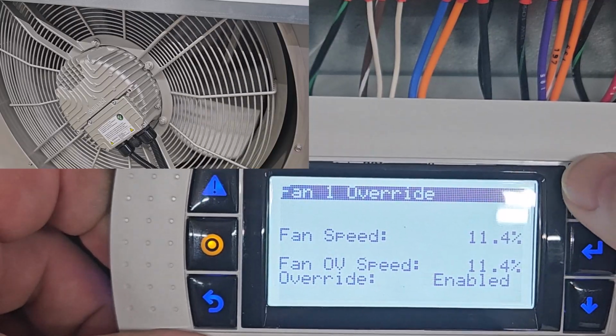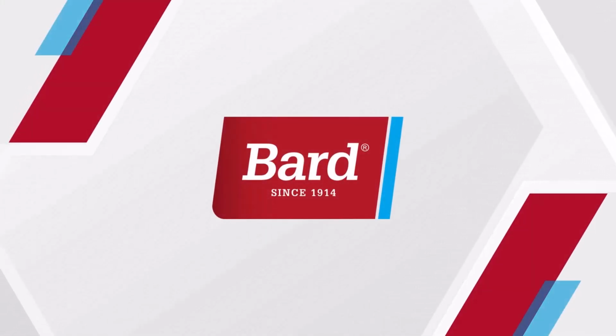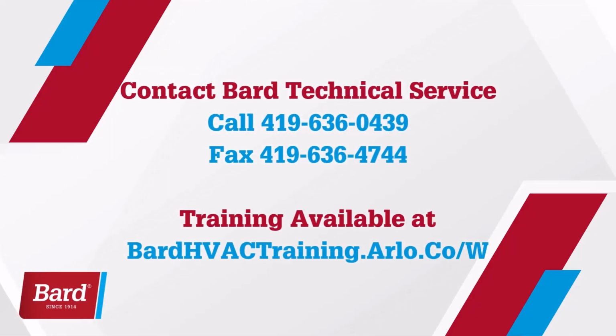Once verification of motor operation is complete, the unit can be placed back into service. Don't forget to install the electrical panel and leave the unit better than you found it. That concludes the removal and installation of the MEGA-TEC condenser fan motor. Please don't hesitate to call if you're experiencing any issues.